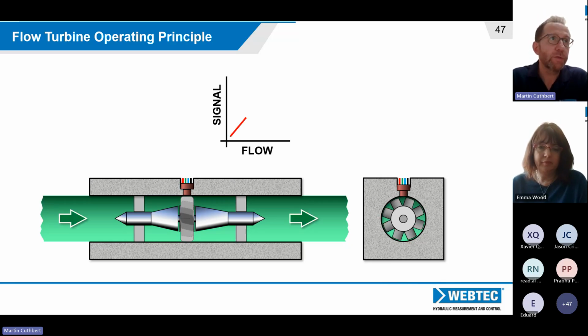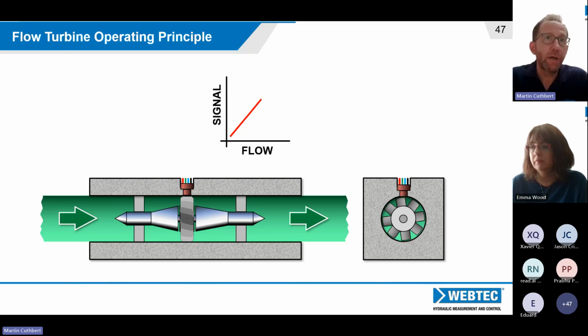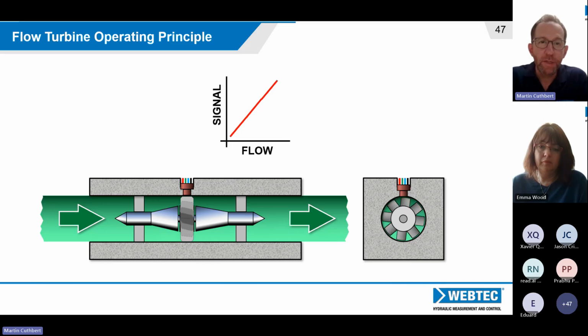If we were to put some oil through that, you'd see the turbine start rotating, and broadly you get a signal proportional to the frequency of rotation. Clearly, if the flow goes up, the frequency of rotation goes up and the signal increases. That's very crudely how it works. We also have electronics and software built on top of the flow meter, because the relationship isn't exactly linear, and you want the widest possible range of flow measurement - from the lowest flows up to the highest flows, what we call the turn down ratio. To achieve that, we do some clever maths inside the conditioning circuit to ensure an accurate result over the full flow range.